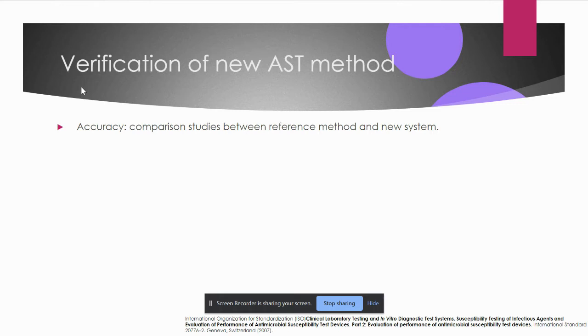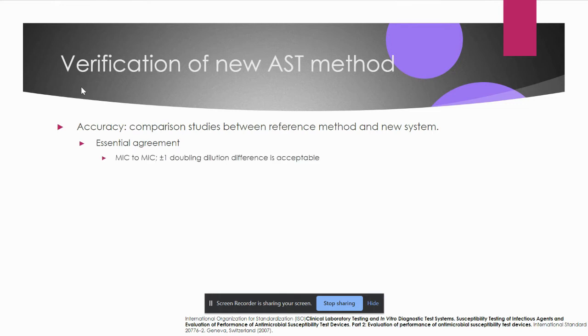As an example of verification of a new AST method: suppose a new analyzer is introduced, or you are changing from Kirby-Bauer to E-test or vice versa — for any of these you need to do a verification study. The study includes accuracy, where you perform a comparison study between the reference method and the new system. In accuracy, we look for essential agreement — the agreement of MIC to MIC — where a difference within plus or minus one doubling dilution is acceptable.